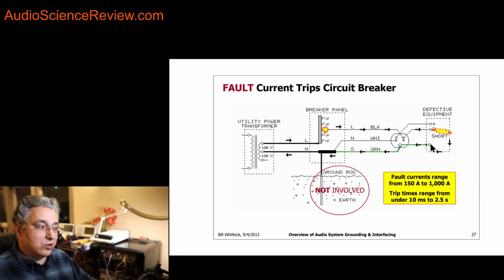So to remove or lower that risk, we take the chassis and hook it up to the third pin of this outlet, and that becomes our ground, going to the same spot. Now imagine this has happened — the hot wire has come loose and connected to the chassis. The chassis is a stout piece of metal, so it has almost no resistance to current, so now we have basically a short circuit. Hot wire comes in, immediately connects to ground, circles back, and completes this circuit. With 100 amps on tap, this circuit now goes from a maximum of 15 amps to 100 amps available to it.